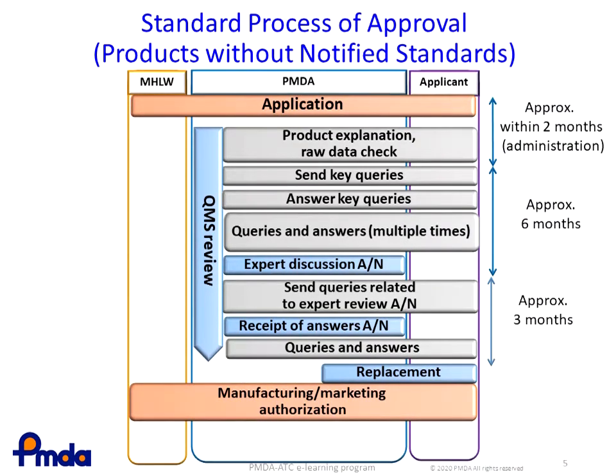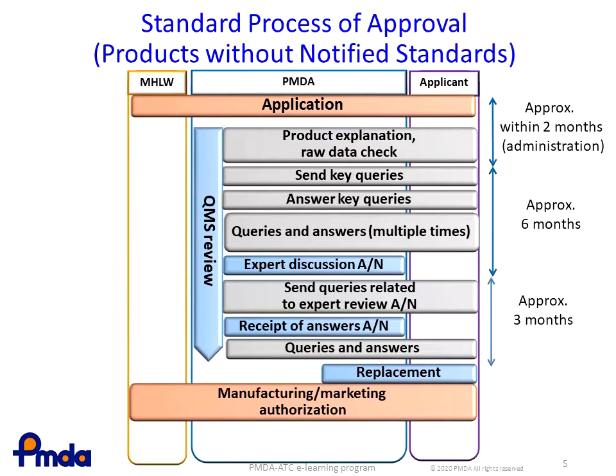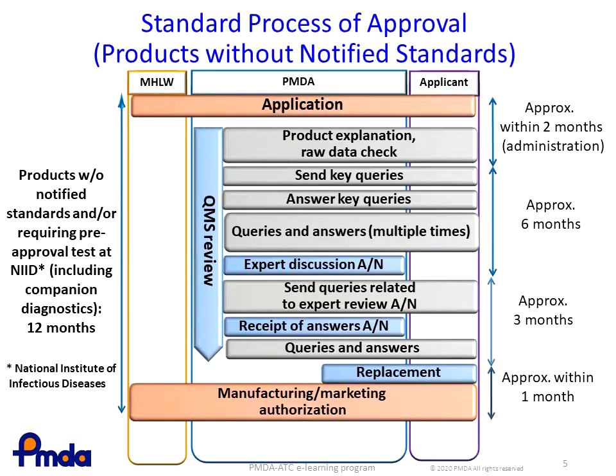After that, the applicant resubmits some of the documents for review, and if they are acceptable, authorization of manufacturing and marketing will be given within one month. In this case, the total time from the application to approval is approximately 12 months. The MHLW publishes committee reports for these products.